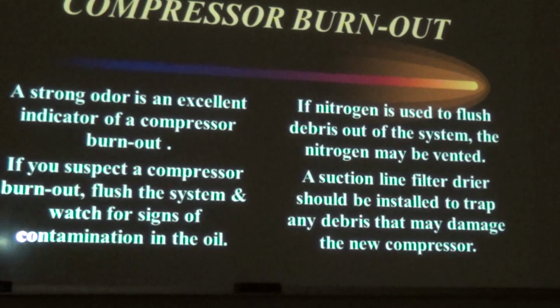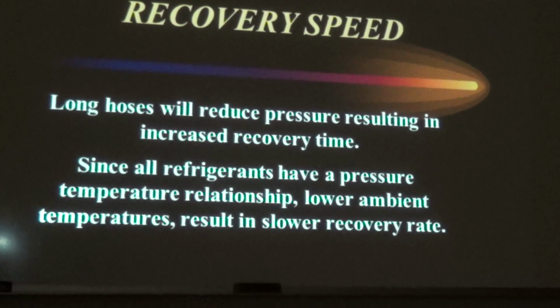You'll find this question in all the sections, 1, 2, and 3. Recovery speed. Long hoses will reduce pressure, resulting in increased recovery time. Since all refrigerants have a pressure-temperature relationship, the two things that are going to impact recovery speed are if it's cold outside, that means lower ambient temperatures, and if you use long hoses. Those will cause the time it takes to remove the recovered refrigerant to take longer.